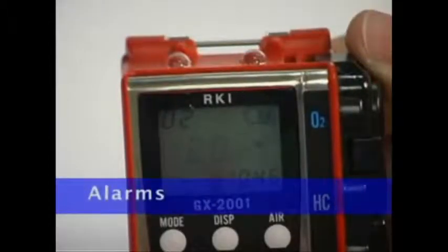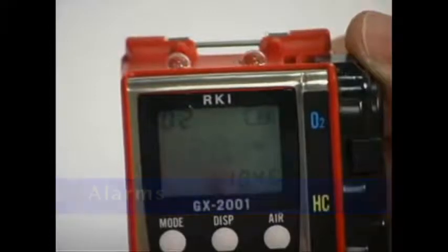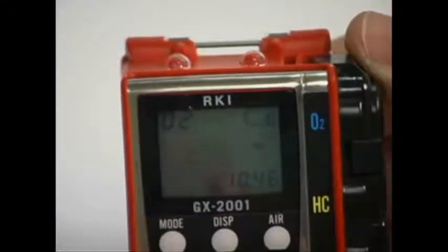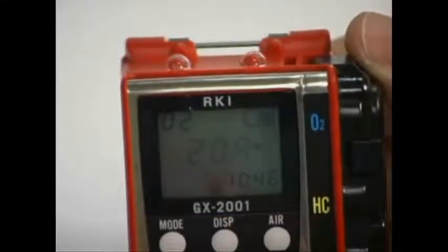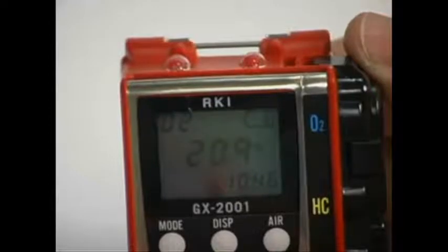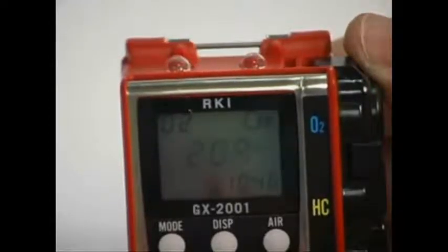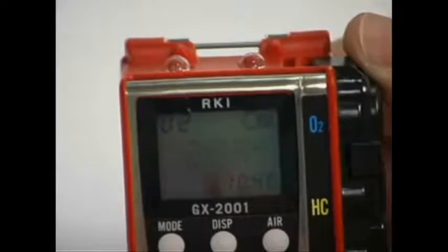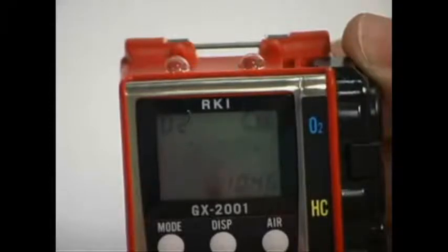The GX-2001 will sound an alarm and the unit will vibrate when one of the target gas concentrations rises above the first alarm point or, in the case of oxygen, falls below the low point alarm setting for that gas. The flashing LED lights, audible tones, and vibrations of alarm 1 will alert at a rate of once per second. Also, the LCD will display the name of the gas in alarm, the backlight will turn on, and the gas reading flashes.